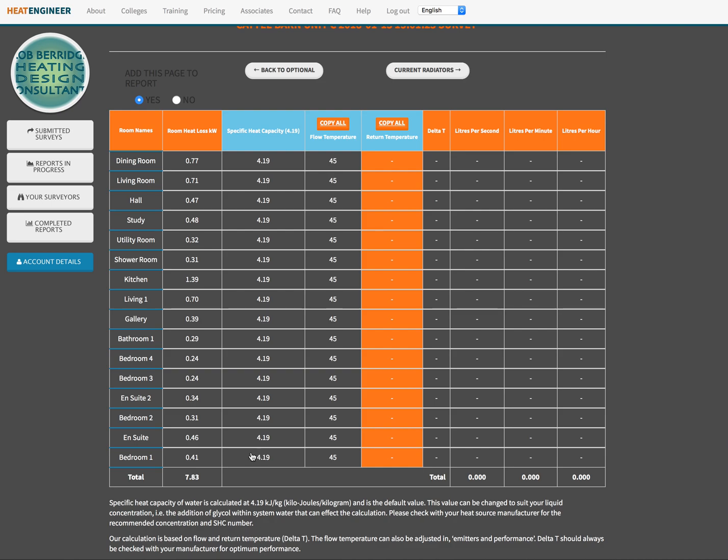Once you've got that, ask them then for the specific heat capacity number. It can change quite a lot. I know that certain glycol mixes that you put in can drop that number down to about 3.5, 3.7, so it's well worth checking it out because it will affect your flow calculation.